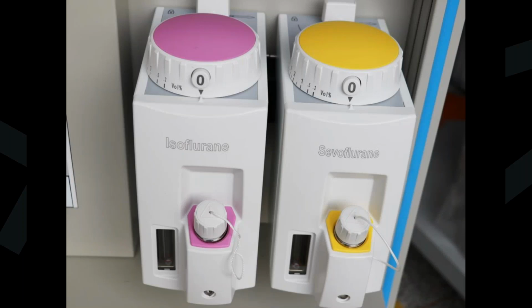And I looked around and checked the obvious suspects, which is normally the patient circuit going to the patient, for leaks, because those patient circuits can be rather cheap and poorly made. So I checked the usual spots and I couldn't find the leak. I was really concerned that I might have a rather major leak going on inside the machine, because everyone in the room was fairly drowsy and unresponsive, and I was starting to get that way myself.